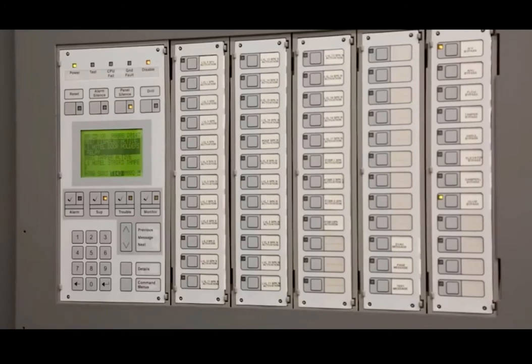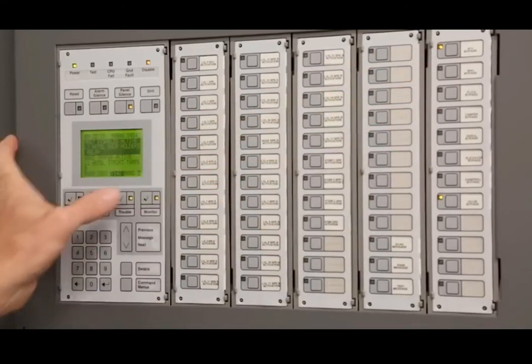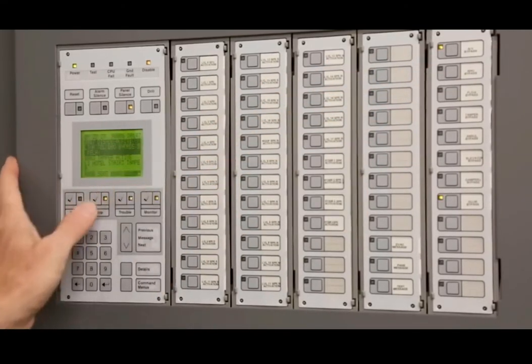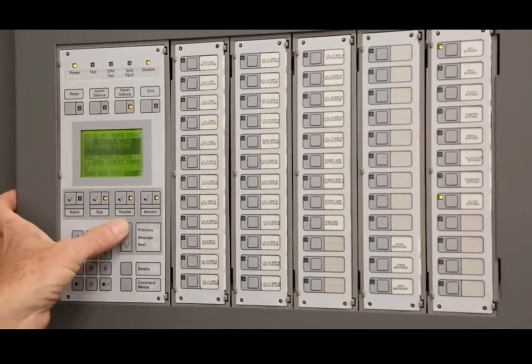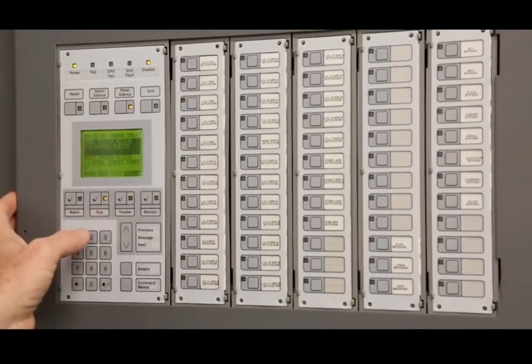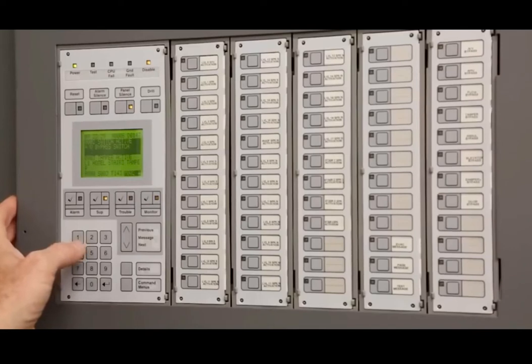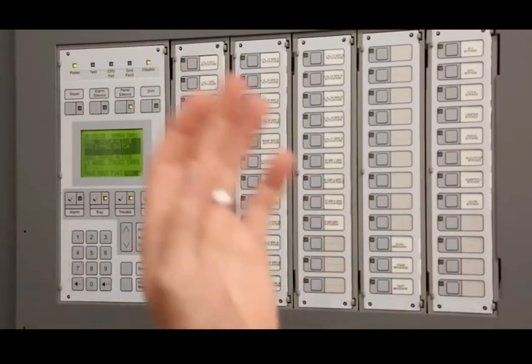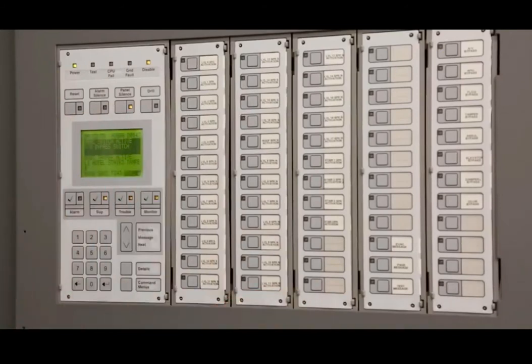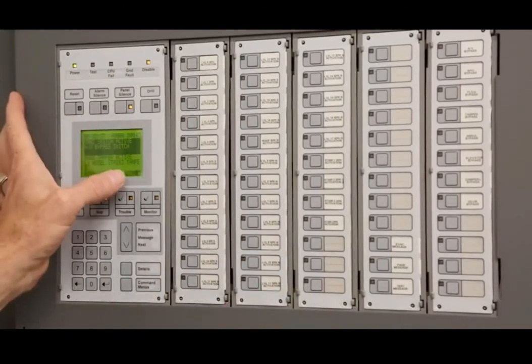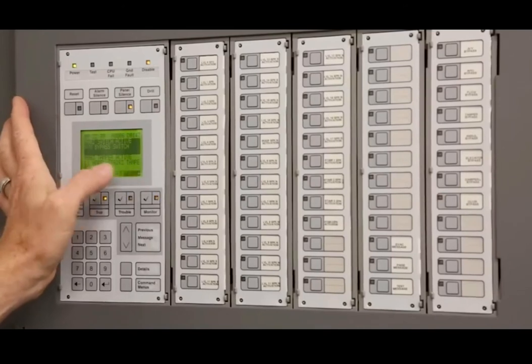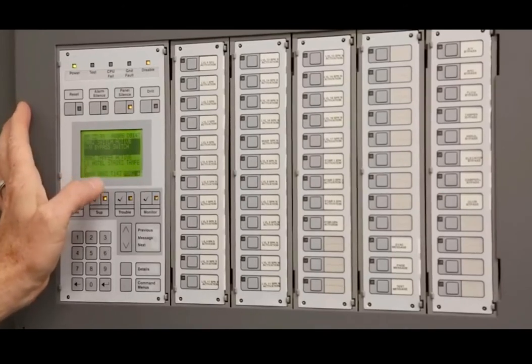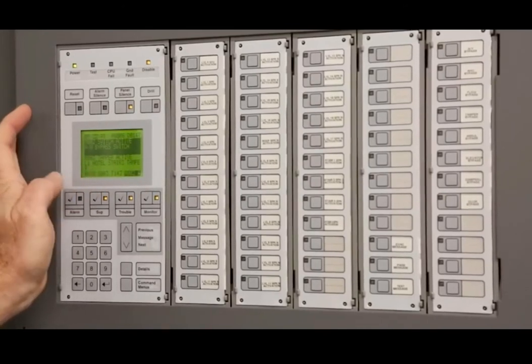Again, like I said, if I just hit that other button right there, the monitor, if you notice, it went up to 2 points, and you can scroll up and down on that also, and it'll say AV bypass switch is activated, okay? So monitor points, like I said, are just switch actions, anything on the smoke control panel, any dampers. That does not report to the third party. The dialer does not report monitor points. It only reports troubles, supervisories, and alarms.